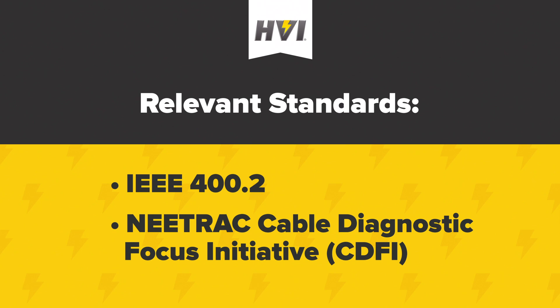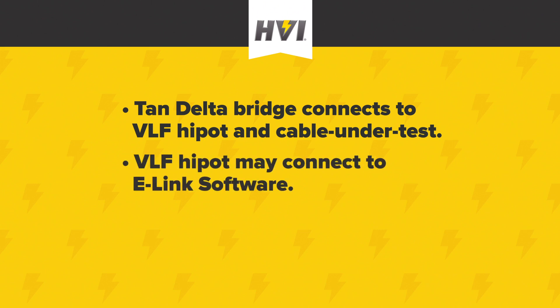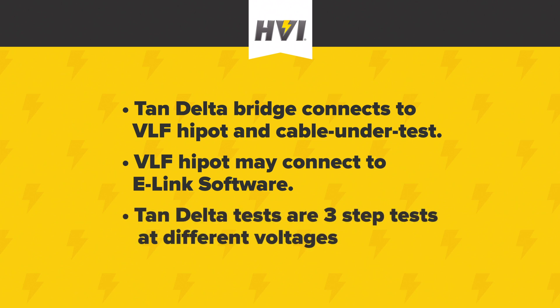Tan-Delta tests require a Tan-Delta transducer or bridge that the VLF-E Series connects to. The Tan-Delta bridge connects to the cable under test. Users may run the Tan-Delta test directly from the front panel of the hipot or remotely using the e-Link software and a connected laptop. Tan-Delta tests require three different stages or levels of voltage during the test, unlike some general withstand tests that may require a single stage of voltage for a specified period of time. We'll cover the three stages in greater detail a little bit later in the video.